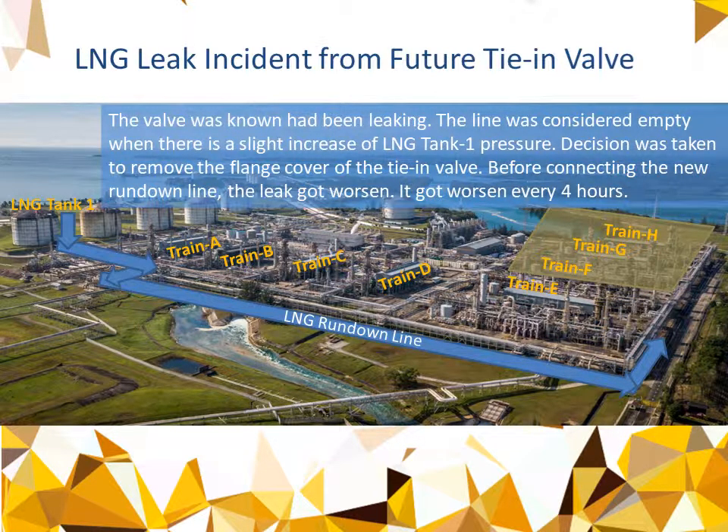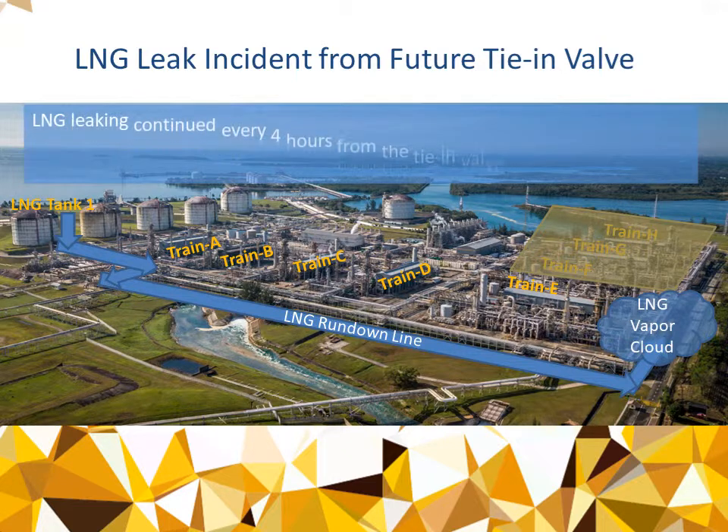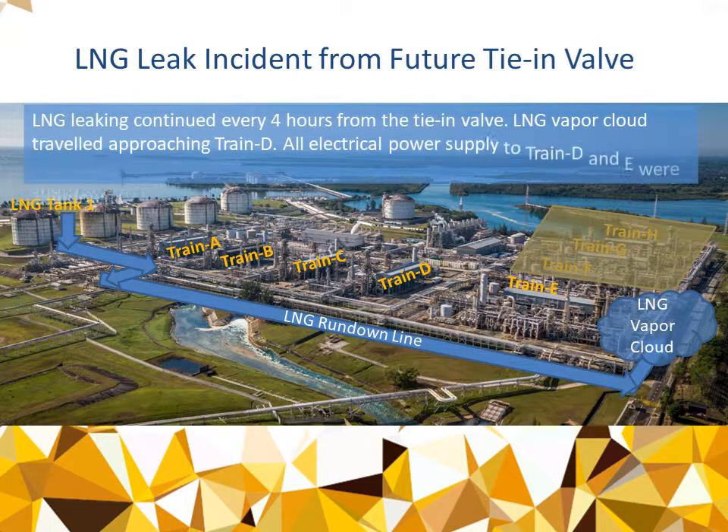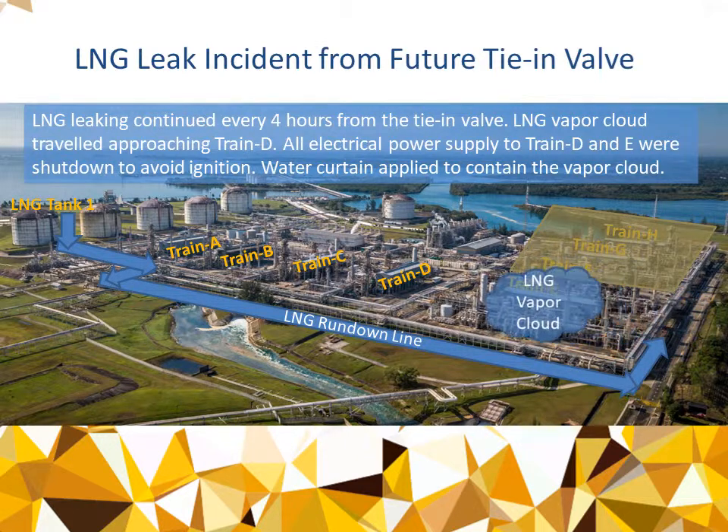The leaking continued, recurring every four hours from the tie-in valve. An LNG vapor cloud traveled and approached Train D. All electrical power supply to Train D and Train E was shut down to avoid ignition. A water curtain was applied to contain the vapor cloud.